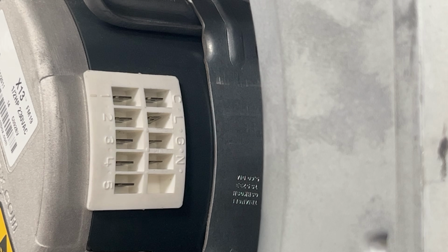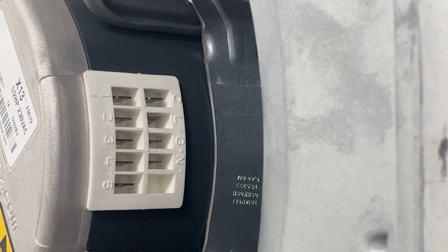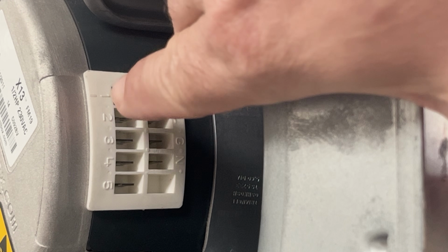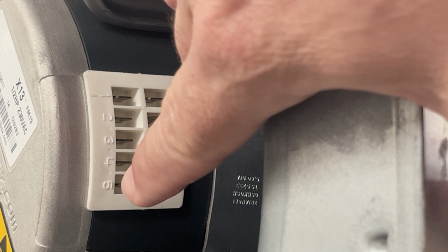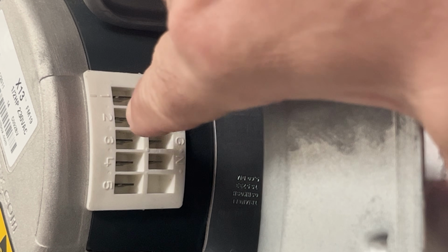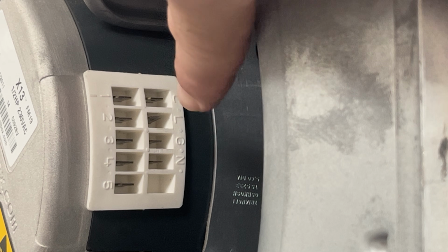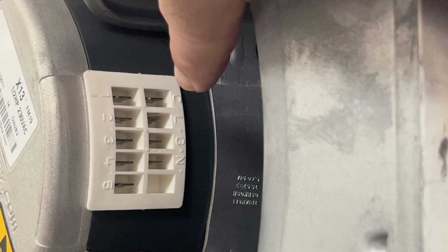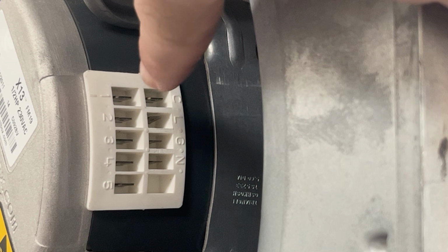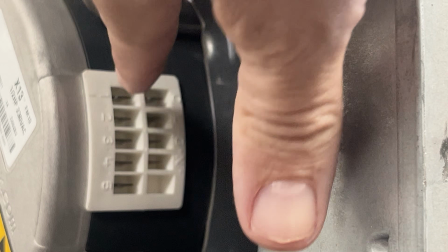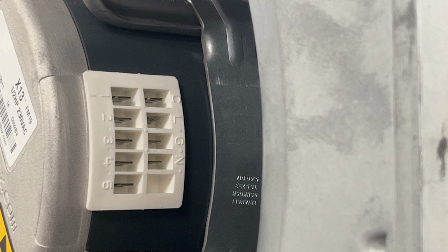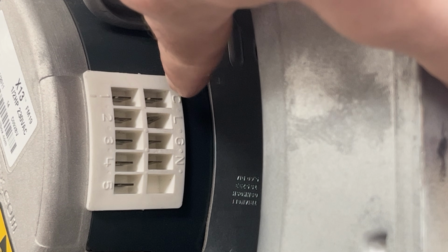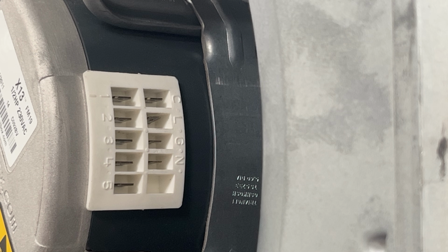Just stay tuned. Okay, so I've got a closer image here of the terminals that we were talking about. 1, 2, 3, 4, and 5. And that's all going to be low voltage. Do not wire any high voltage to this. If you look over here on the back side, I have C, L, G, and N. So C is for common low voltage. So all these front terminals, 1 through 5, are going to be 24 volts input. The back terminal on the very top, C, that will be low voltage out back to the transformer. The L is line voltage, the G is for ground, and the N is for neutral.